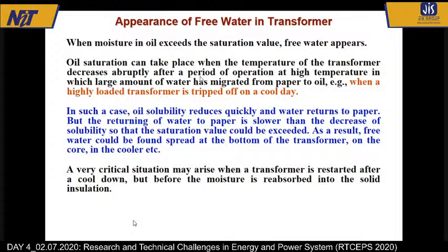Then when the transformer is started again, as you know, the cooling fans start fast. What will happen? They will draw the oil from the bottom of the tank and then through the cooling tubes back to the top of the tank. So when the transformer starts again, these cooling fans draw the oil of the tank and then it will almost like a spray come from the top of the tank on the transformer winding. And the transformer winding... This has happened many times. So people take adequate care nowadays.